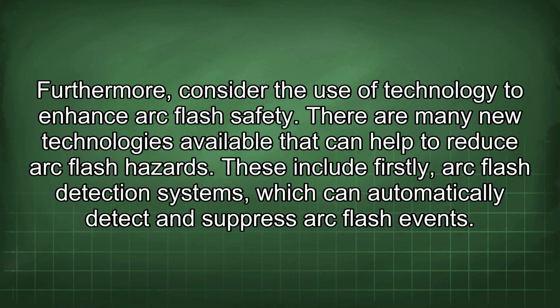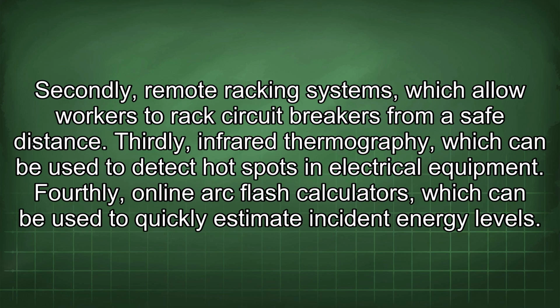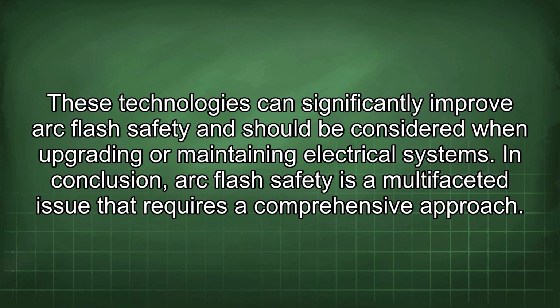Furthermore, consider the use of technology to enhance arc flash safety. There are many new technologies available that can help to reduce arc flash hazards. These include, firstly, arc flash detection systems, which can automatically detect and suppress arc flash events. Secondly, remote racking systems, which allow workers to rack circuit breakers from a safe distance. Thirdly, infrared thermography, which can be used to detect hot spots in electrical equipment. Fourthly, online arc flash calculators, which can be used to quickly estimate incident energy levels. These technologies can significantly improve arc flash safety and should be considered when upgrading or maintaining electrical systems.